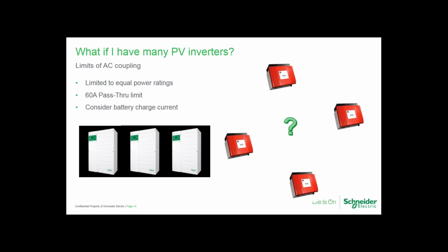We also want to take a moment to touch on the 60 amp power limitation of the internal transfer relay built into each XW. And I think there's a lot of misunderstanding in that regard as well, because 60 amps is the allowable pass through. The actual relay itself uses 30 amp contacts, but there's 3 in parallel. So the problem comes in with surge loads, such as motors, refrigerators, freezers, anything with a motor has a startup current. Locked rotor amps is typically what you want to refer to. So when you have many motor loads starting, especially simultaneously, we can typically get between 5 and 7 times the continuous current rating of that motor just for startup.